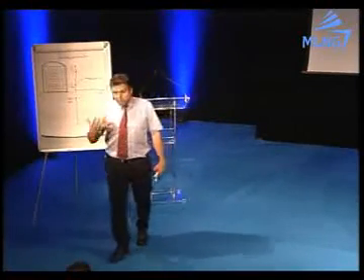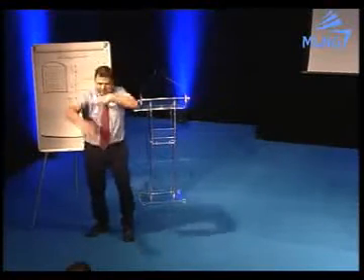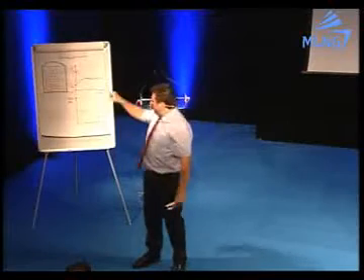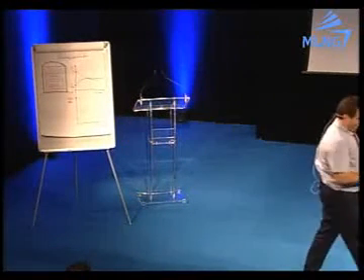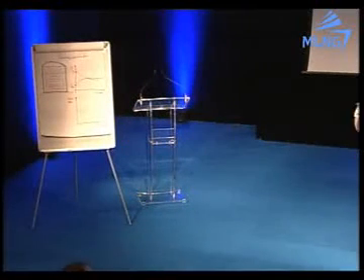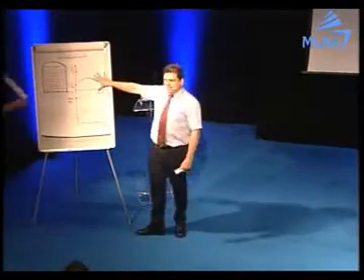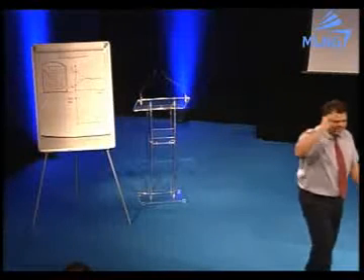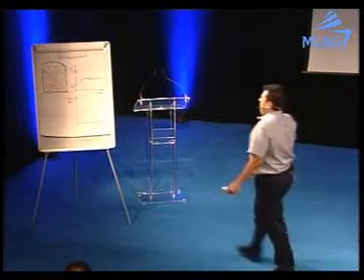So we can have a rollover, because in the tank we suddenly have a mixed mixture, and the pressure of the tank will increase suddenly. This is a dangerous situation for a tank. We don't want a stratified tank, because it's a potentially dangerous tank.